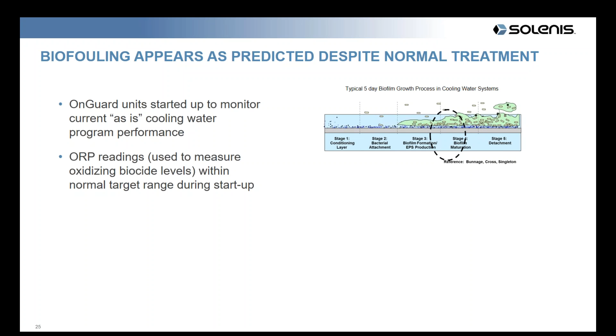What we observe is when we put an OnGuard unit on the system at startup, we like it to monitor the current cooling water program as is, with no special changes. What we'll typically see is that the ORP, the oxidation reduction potential, used as a measure of how much oxidizing biocide, often chlorine, is in the system, is within the normal range. So there's an expectation that since that level's in range, everything must be fine.